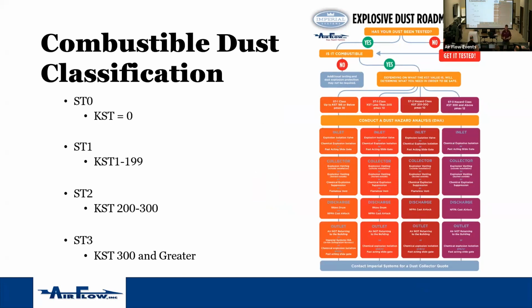It'll give you your dust collector protection. It'll run through what discharge is required. And then on your outlet side, whether you're returning air to the space or not returning air to the space, or in some cases, your KST could be high enough that you're not allowed to return air to the space. So this is a good one to keep at your hand when you're doing dust collection, share it with your owners, share it with the people that you're working with to make the decisions. The architects that don't believe that dust is explosive.